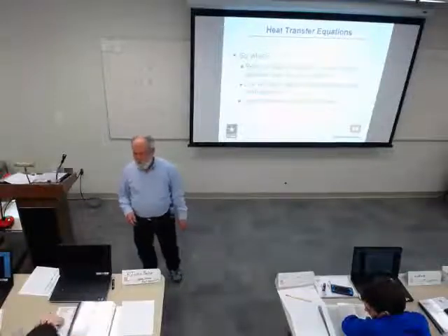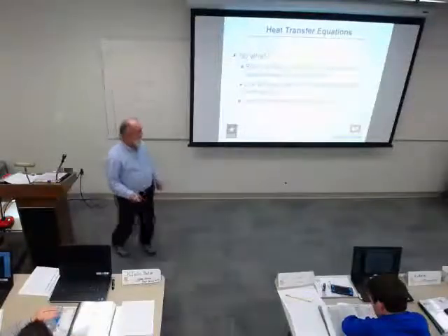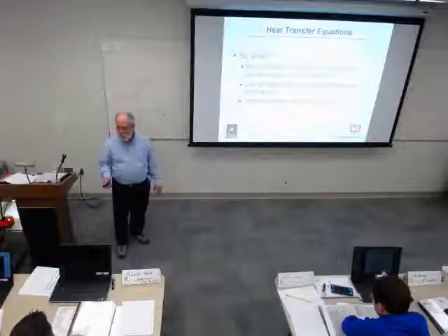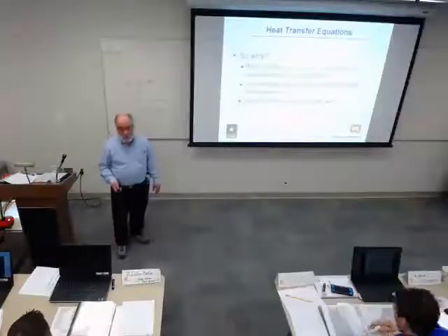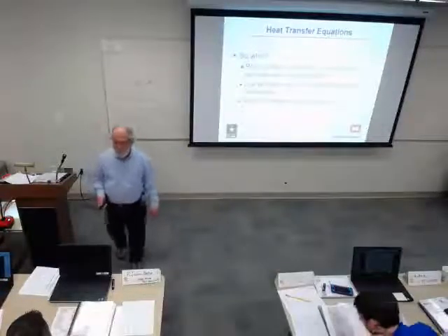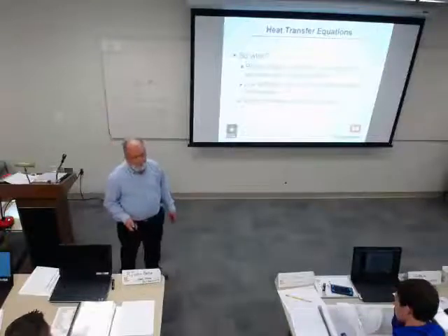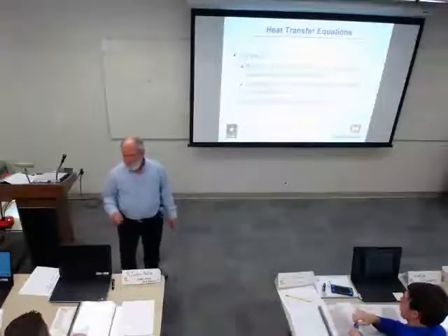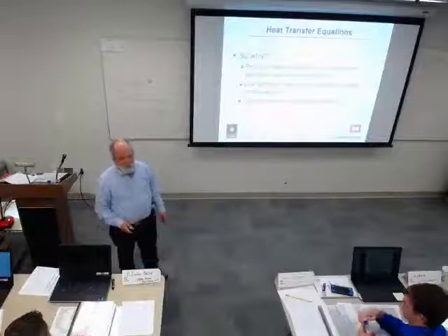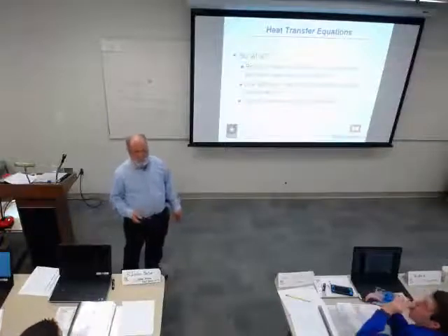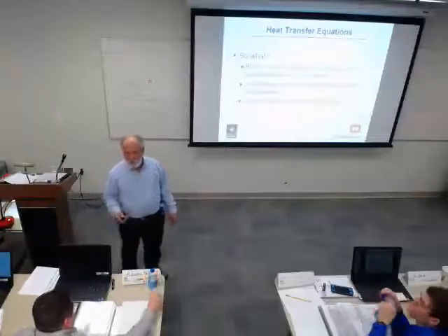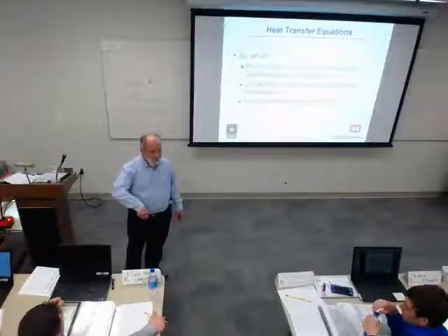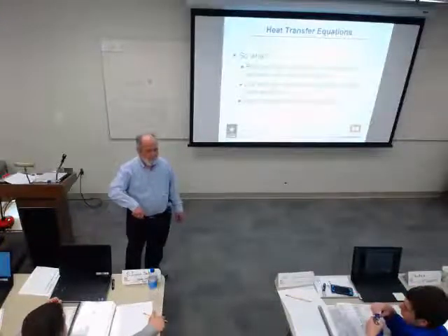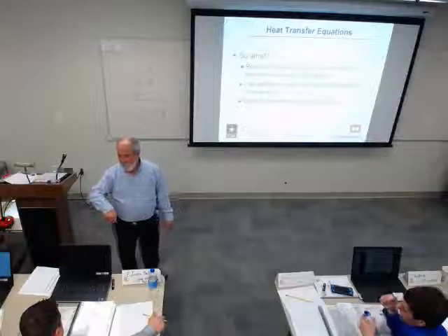Now, right now, that's our governing principle for designing spaces with the kind of loads we have. Loads are changing, and at some point, we're afraid of what we're going to see is that instead of using the sensible heat, we may end up going to some other parameter for determining what the temperature should be, or how to maintain the conditions. Because latent loads now, in some cases, are becoming more dominant because of all the things we're doing to kill the energy consumption inside of the envelope.